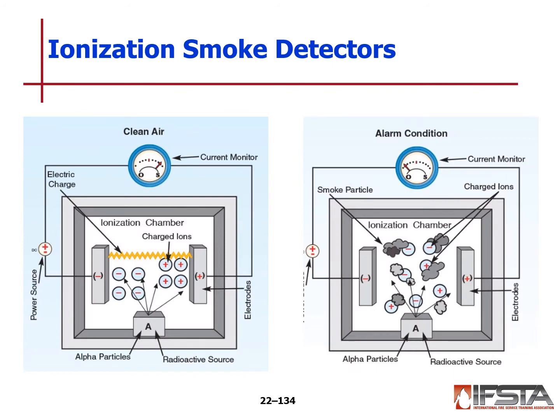With ionization, you've got electrical particles with an electrical charge that are going back and forth between an anode and a cathode. Basically, when that gets disrupted, then the signal is disrupted. You're breaking the circuit, if you will, that will then trip and send the signal to the alarm. There is radioactive material that's causing the alpha particles to go back and forth.